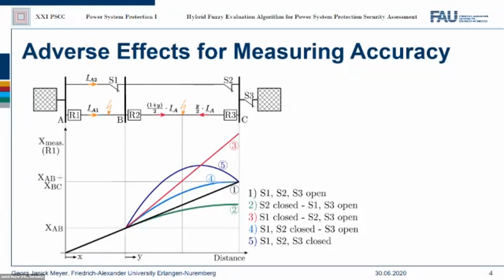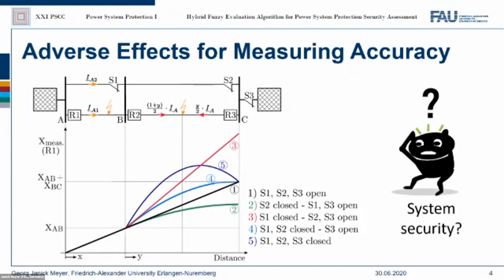line BC. But if we close, for example, switch S1, the relay R1 measures just half of the actual short circuit current supplied by the source, and this leads to a higher reactance measurement. The relay R1 assumes the fault to be much further away than it is, which can be seen from the red line, number 3. Similar negative effects for measuring accuracy can be noticed if other switching stages are analyzed. In this case, for example, also number 2, number 4, and number 5, depending on the switches. So the question is, how do we review protection system security?